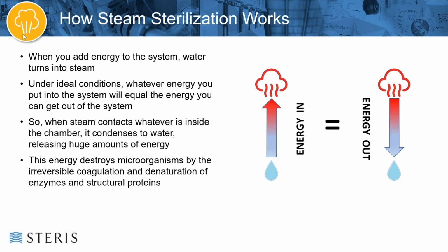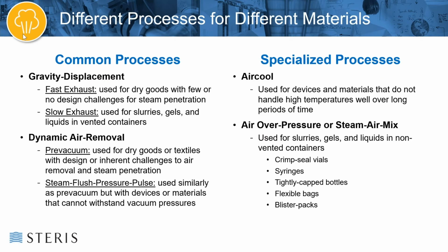So there are different processes for different types of materials when it comes to steam sterilization. The two most common processes are what's called a gravity displacement process, and a dynamic air removal process. With gravity displacement, at a high level, you have two variants: a fast exhaust and a slow exhaust. The fast exhaust is most often used for dry goods or hard goods, with few or no design challenges for steam penetration. Slow exhaust is often used for slurries, gels, and liquids in vented containers.